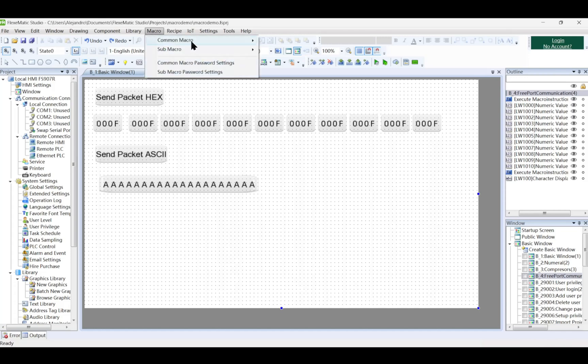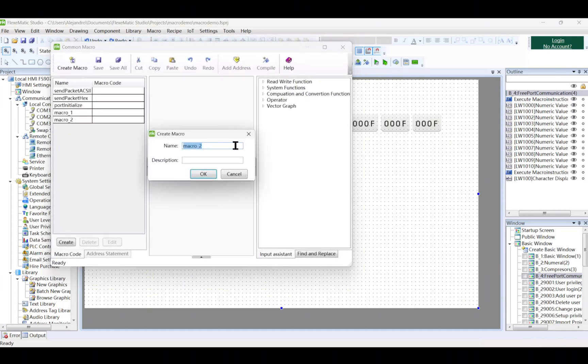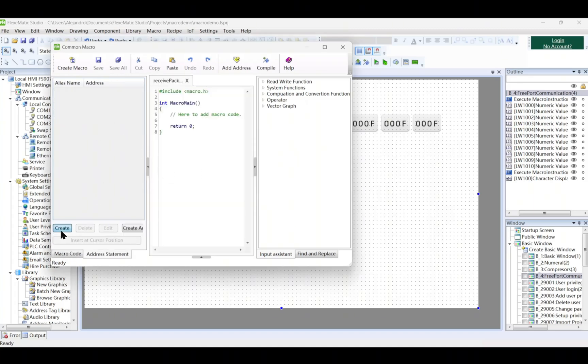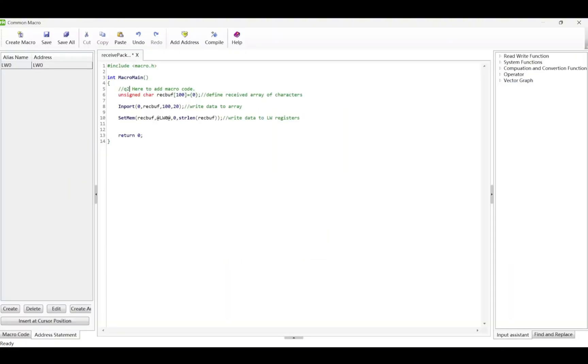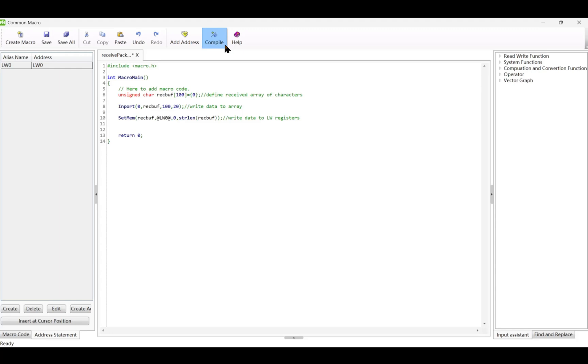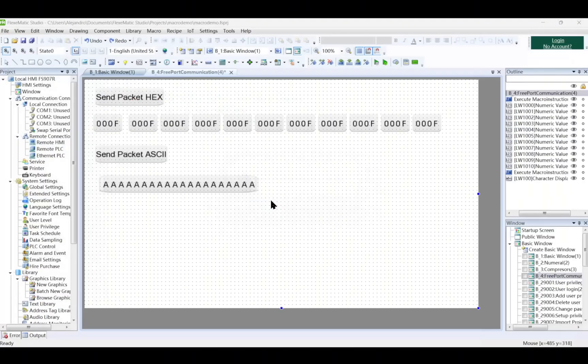To create a script for receiving messages and reading incoming data from the serial port, we define an array RecBuff of 100 unsigned characters initialized to 0 to store the received data. The import function reads data into the RecBuff array, with parameters specifying the port number, buffer number of bytes to read, and a timeout value. Finally, the SetMem RecBuff at LW0, at 0 strlen(RecBuff) function writes the data from RecBuff to the LW local word registers, with parameters including the source buffer, destination register, starting index, and length of the data to be written.